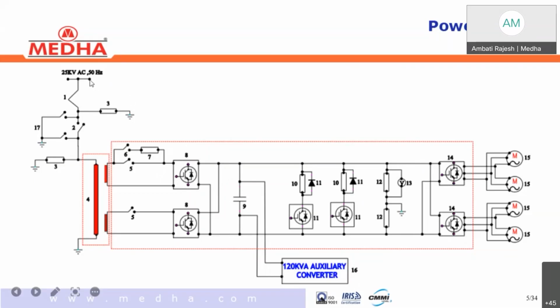Continuously the line converter measures the OHE voltage and converts the DC into single phase AC, such that in the traction transformer primary it generates more than the OHE voltage. So like that, the line converter works and converts that 1800 volts DC into single phase AC. The same will be given to the traction transformer secondary.